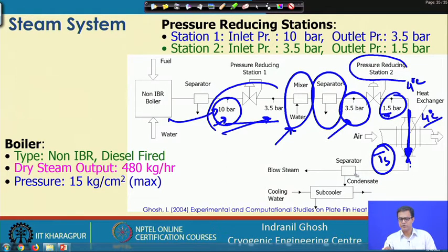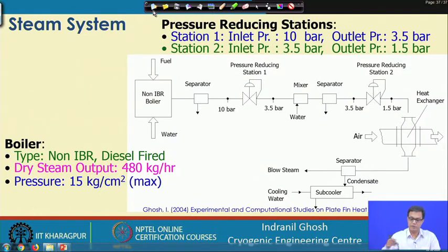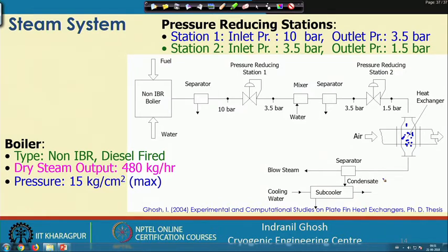The steam that is used in this process is about 3 to 6 times the part that is getting condensed. This excess steam is used because we do not want any accumulation of the steam condensate on the steam side. If the steam gets condensed and that condensate accumulates on the steam side surface, that will reduce the heat transfer coefficient. So, we want drainage of that condensate, and that is why we use the excess steam, which will remove the condensate from the test channels on the steam side.